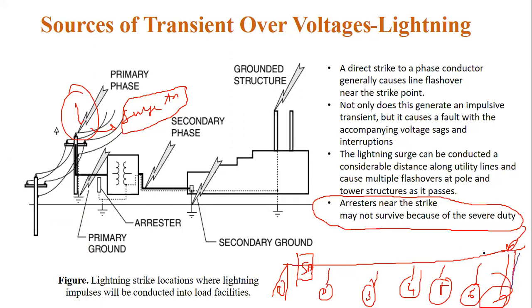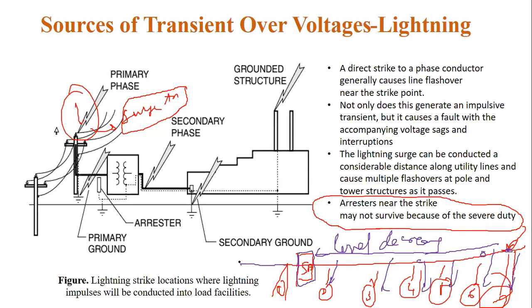Now see here, flashover, grounded. At each and every pole it is grounded. So when it comes to this place, the level of that voltage decreases. I'm not saying it clears the fault, but some amount of voltage decreases when it comes to this place. Now that amount is again cleared by the surge arrester. But before the surge arrester clears it, some amount of voltage is injected into the loads. That may lead to impulses, voltage sags or some interruptions.